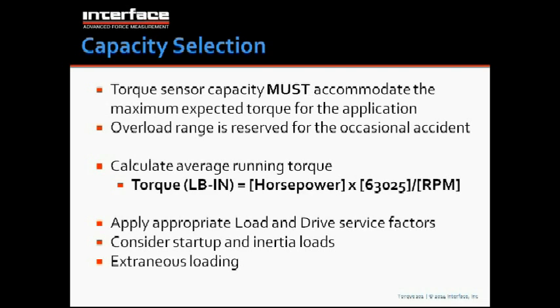The overload range is reserved only for the occasional accident, so you'd never plan on using anything more than the capacity of the sensor. In many cases, torque is a little harder to get a feel for than load. How much torque is there really in the system? A lot of times people have to calculate it, and you can do that by looking at the horsepower and the RPM. Once you have that, it's called the average running torque. And then there are load and drive factors that can be applied to that to actually estimate what the probable peak torque may be. And it can be considerably higher than the average running torque. You also need to consider startup and inertial loads and any extraneous loading.